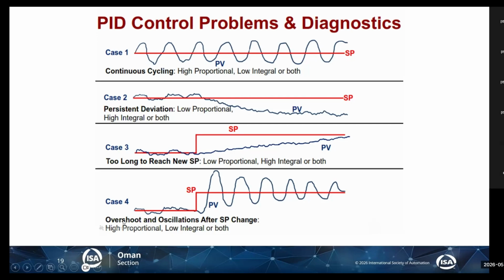Here you can see I made a step. It is overshooting. Now the overshoot is less and less and less till it is settled. So it is oscillating, but not the same as this one. This one is consistent, frequent oscillations. But here the oscillations are initially big, and then they are getting smaller till they settle to the set point. And this can be because of high proportional, low integral, or both.